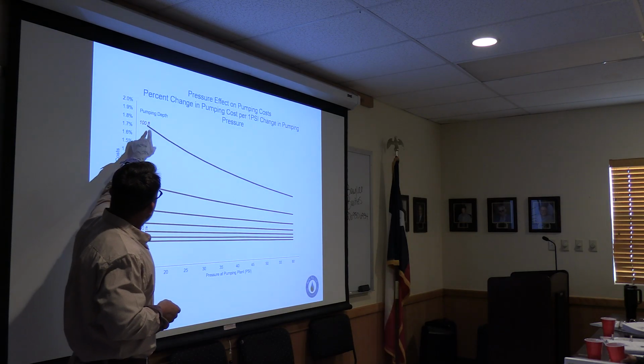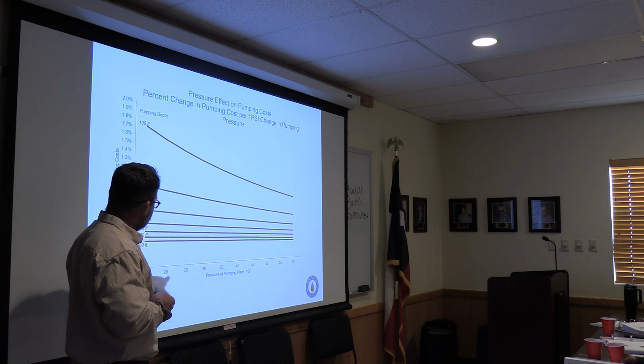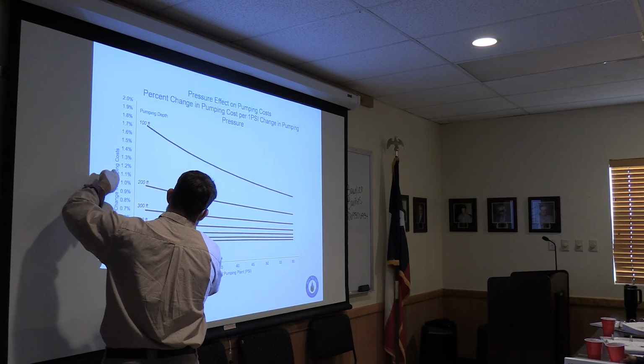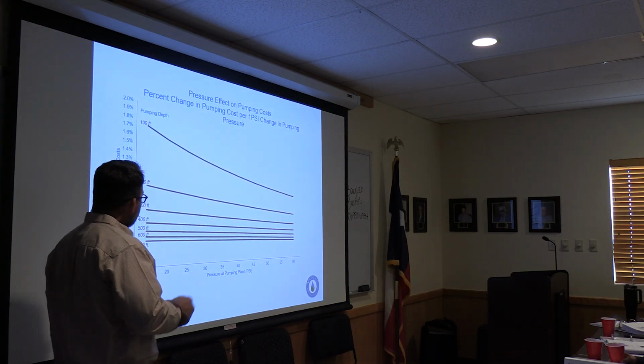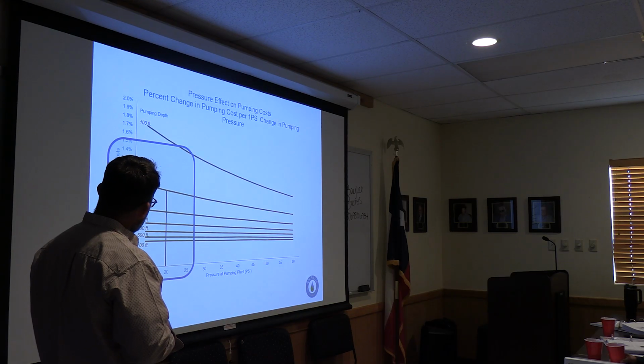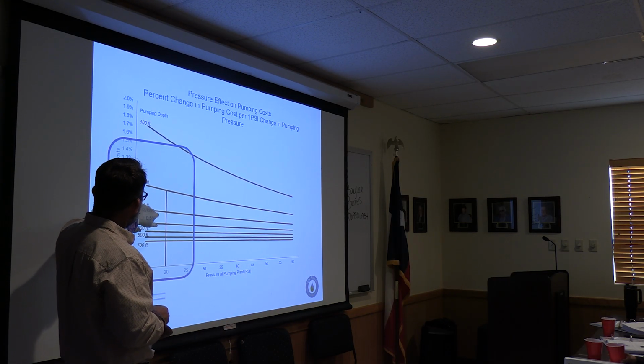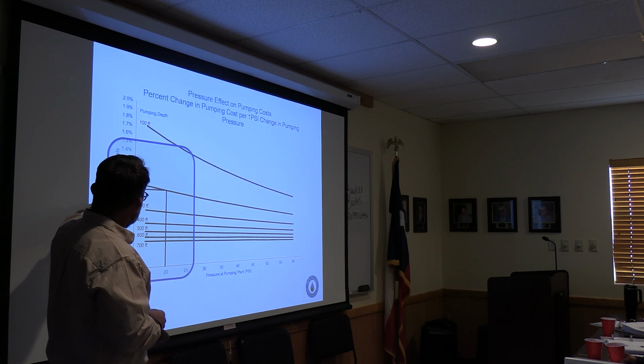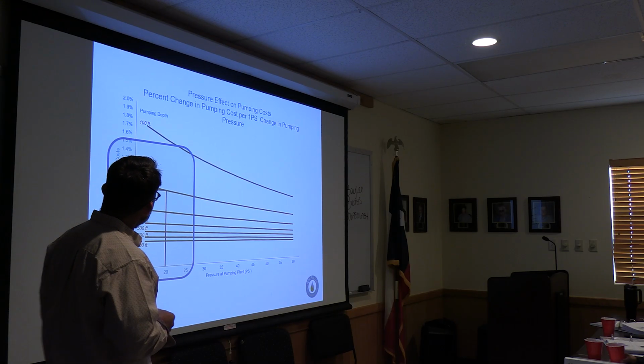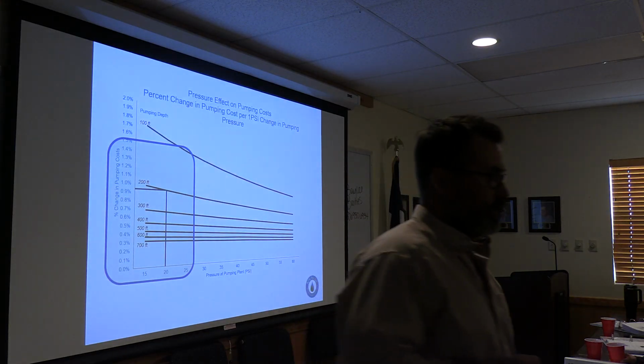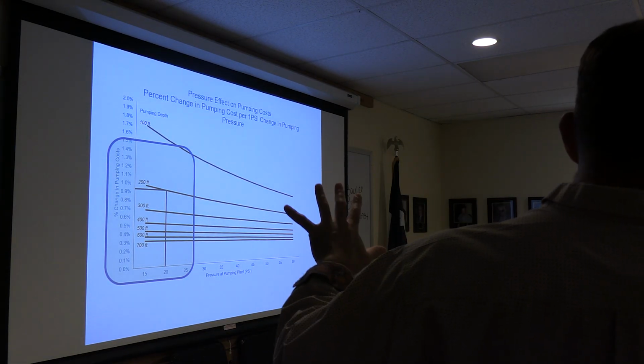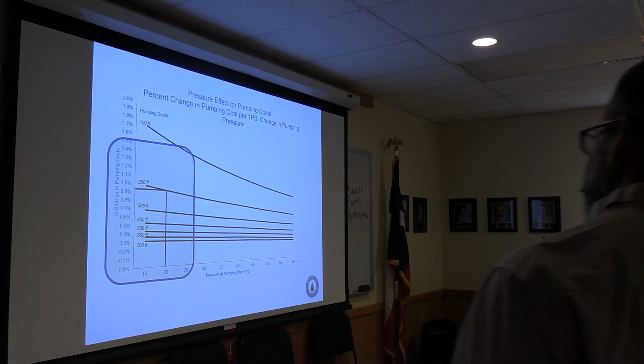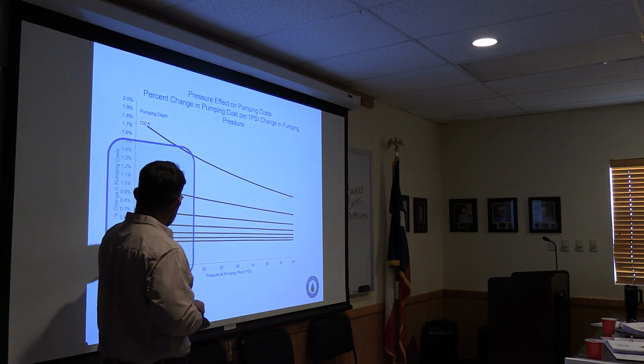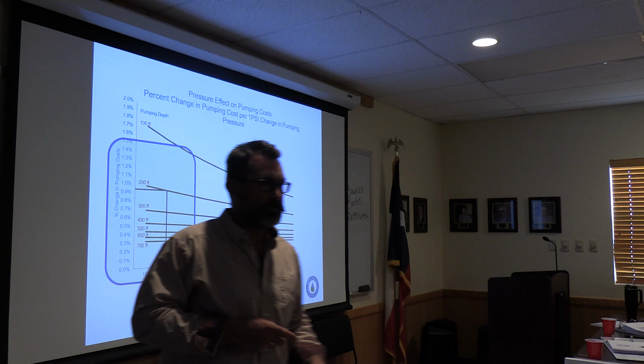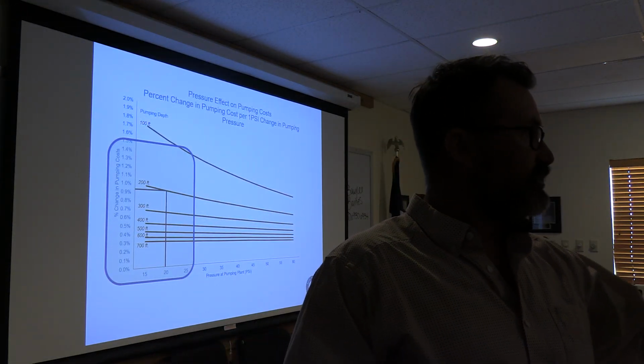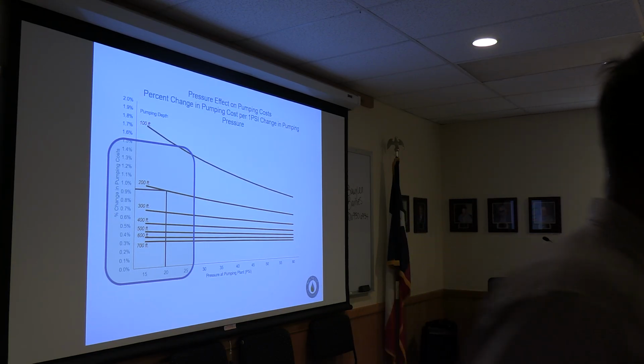So the idea would be if this is your pumping depth, from 100 feet, 200 feet, 300 feet, etc., and your pumping pressure from 15, 20, 25, etc., you would look from this pressure and where you're pumping from, and there's some overlap or some index point on there. Where you can say I'm pumping at 20 psi and I'm pumping from 200 feet. What I can see is roughly every single change in pressure is worth a 1% change in my pumping cost. Remind you, this is busy and nerve-wracking to get your head around this. But the example is if you do something that's worth 20 psi, in this scenario, that's a 20% change in your pumping cost. So if you want to impact your bottom line by reducing your pressure losses or your system losses along the way, this is a way that you can tell how impactful this could be.